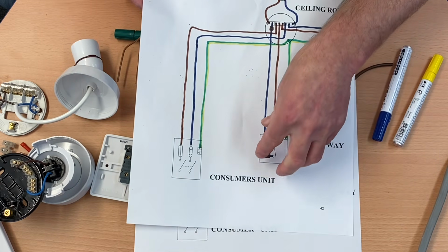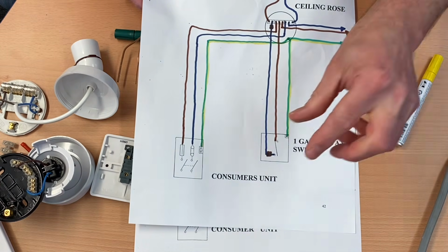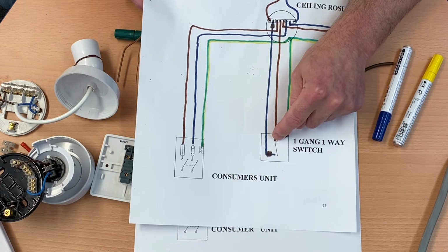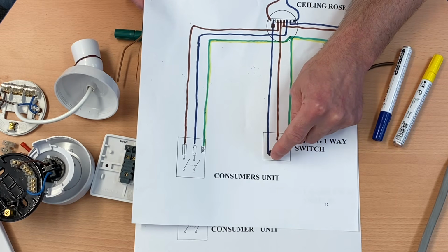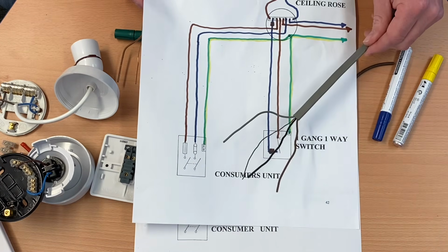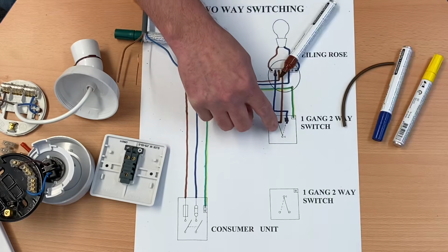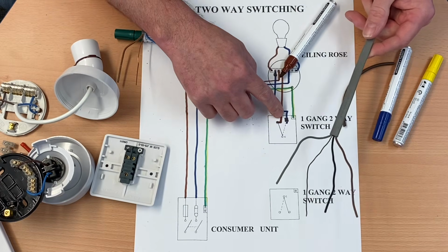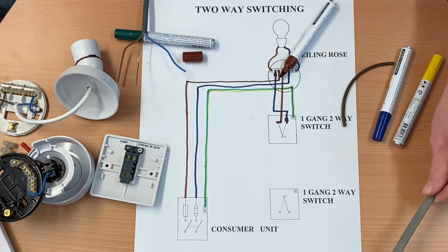In the real world, all you need to do is leave that cable in place, take off the one-way switch and replace it with a two-way switch, making brown and blue with brown sleeving in L1 and L2, and then just introduce a 3-core from the switching position you've already got to a new switching position. So that's what we're going to do here. So this is just simply one cable from the switch to the other switch, 3-core and CPC.